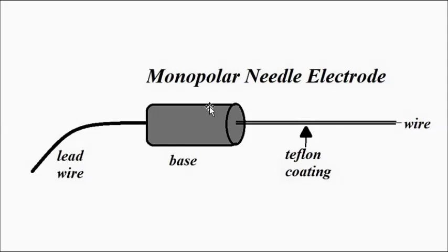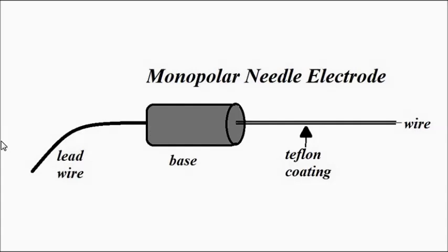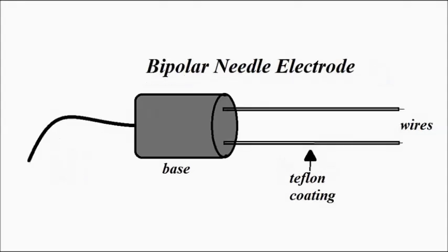Here you can see the monopolar needle electrode: the base is generally made of metal, then we have the thin wire with Teflon coating, and it is exposed at the tip so that it can be inserted into the specific body part. The lead wire carries the signal to the signal conditioning and processing circuitry for output. The bipolar needle electrode is the same, but consists of two Teflon-coated wires instead of one.